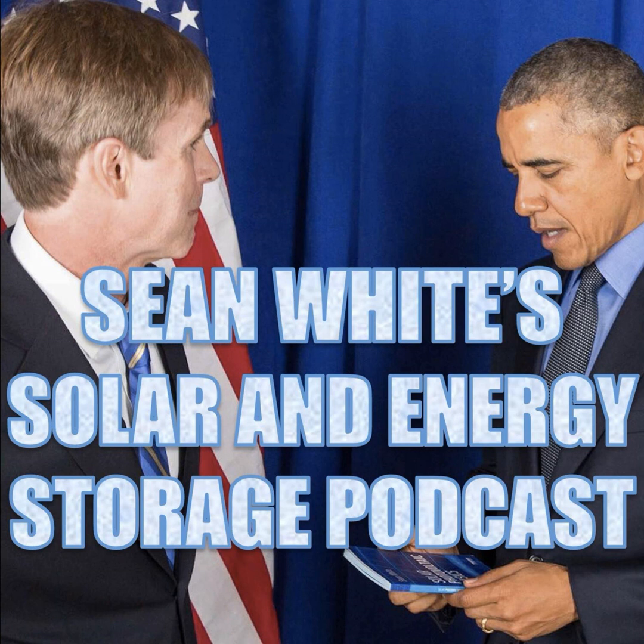I'm sure. Nowadays, we call things functionally grounded instead of ungrounded and grounded like we were before. So if you hear people talking about a grounded inverter or ungrounded inverter, you know they're talking about the 2014 NEC, 99.9% of the time. And so functionally grounded is a system that has a ground reference that is not solidly grounded. Reference grounded system, low resistance electrical reference to ground. So we could say perhaps that is the fuse grounded system, which is also another type of functionally grounded system. I'd say in most cases, a reference grounded system is actually a resistor grounded system.